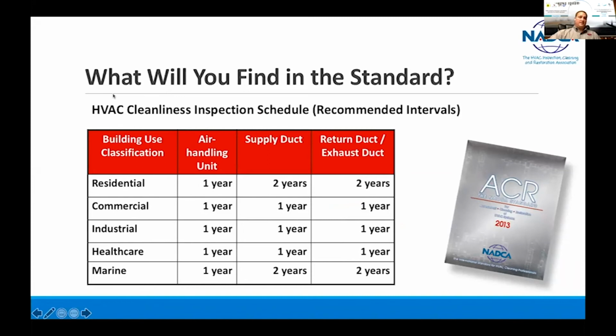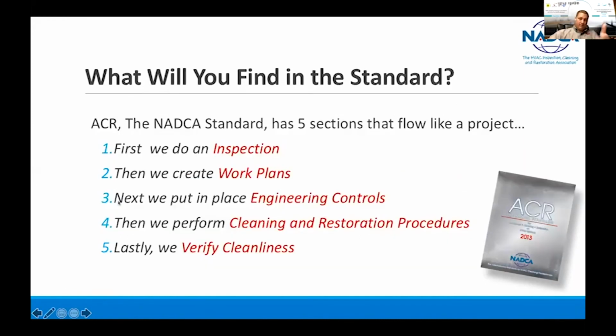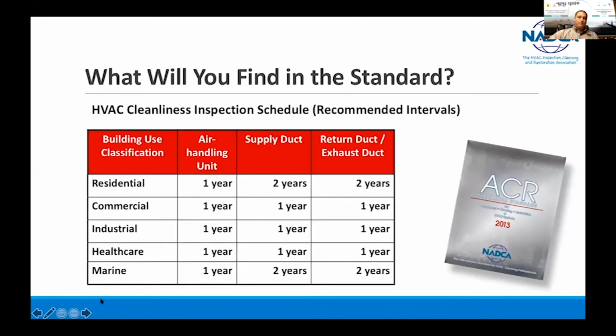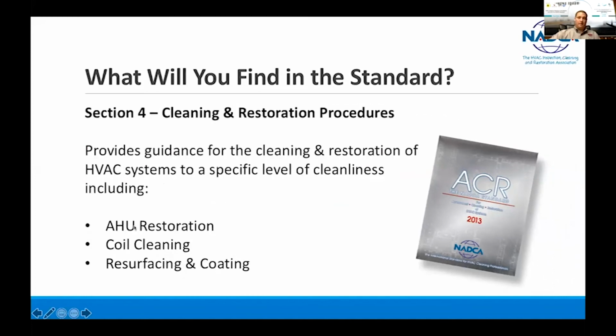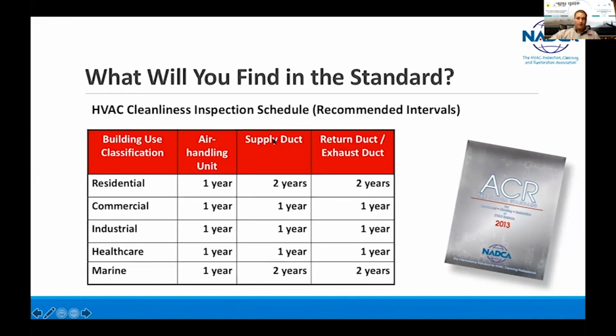HVAC cleanliness inspection schedule. So these are when we should go back through this. Right here, residential is 1 year, commercial is 1 year, industrial is 1 year, healthcare is 1 year, marine is 1 year. But please look here, we start focusing in on certain aspects, whether it's the air handling unit, supply ductwork, return ducts and exhaust ductwork, and these intervals change. This is a good graph to always refer back to when determining the need for cleaning.